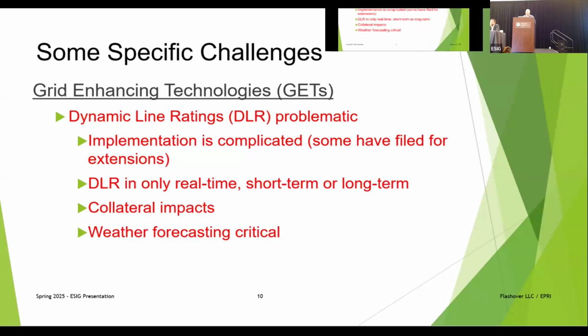If I up the capacity of a certain line based on the weather, 20%, what happens to protection systems, breakers, substation equipment? You can't just put more current on the line without worrying about the rest of the equipment that's in series. And again, weather. Some DLR has monitoring equipment. That's good stuff, but others are just implementing it based on a forecast. So now you've got to worry about your accuracy.